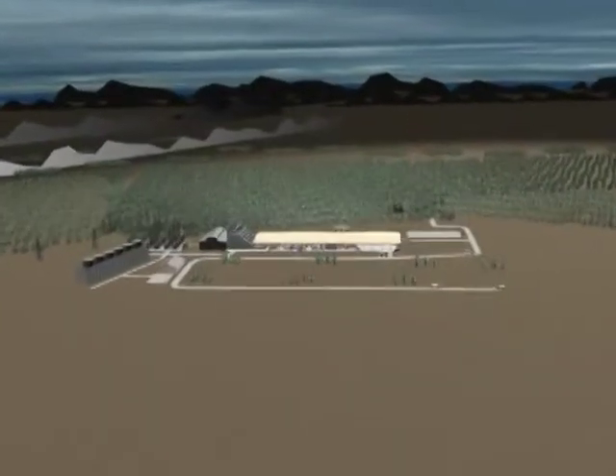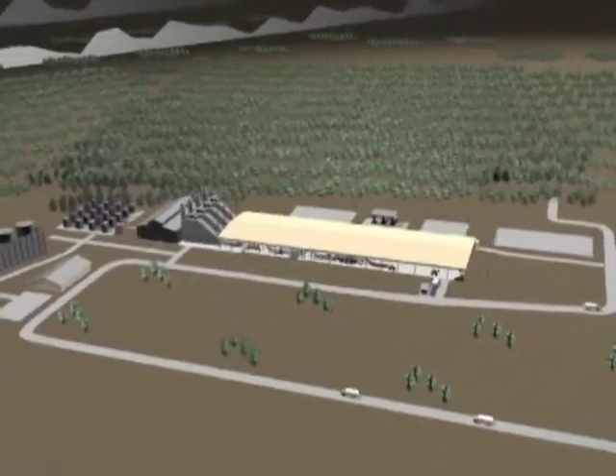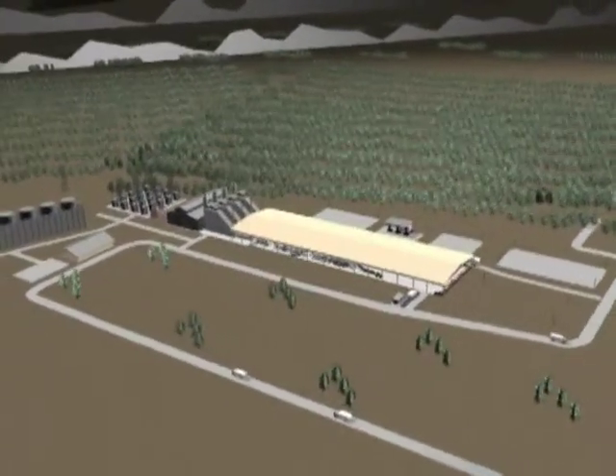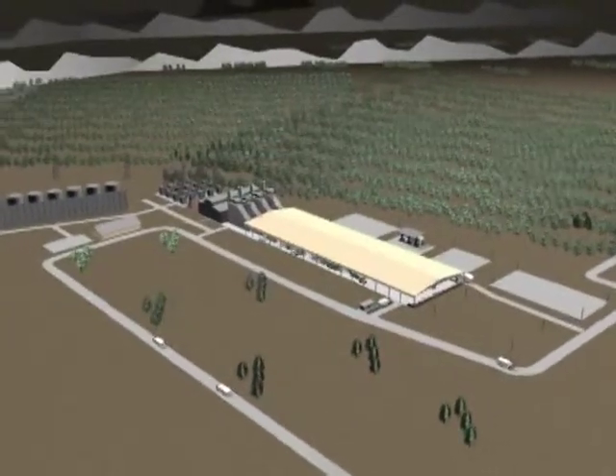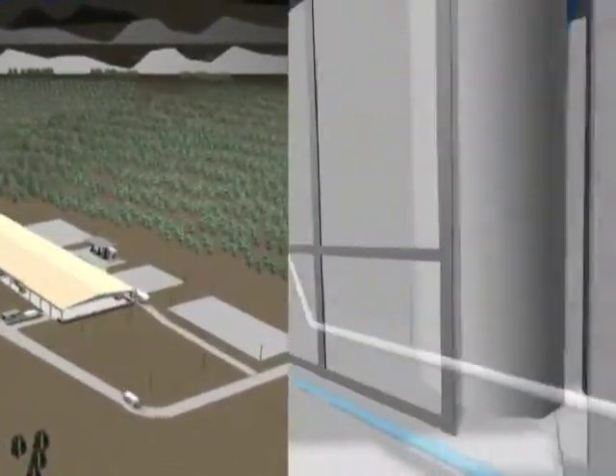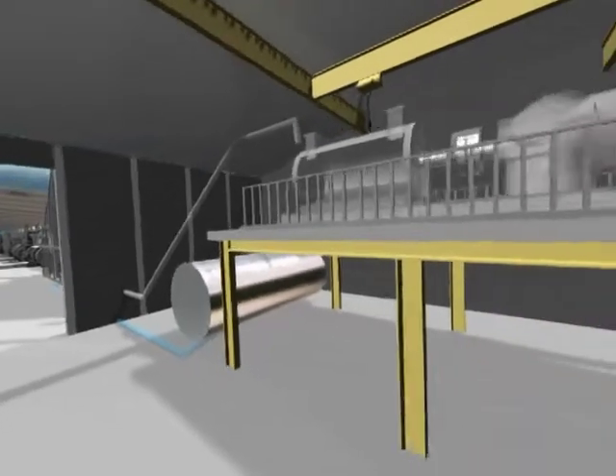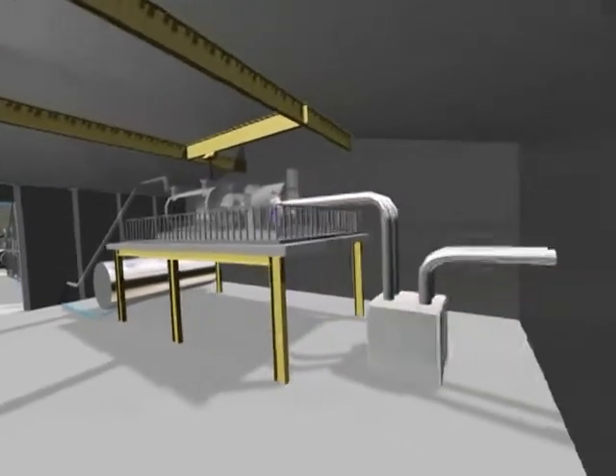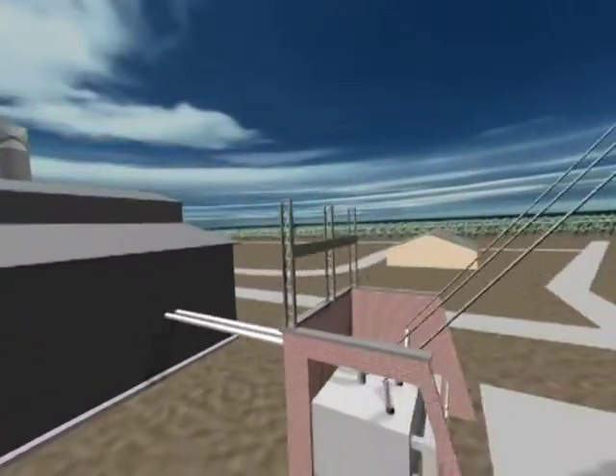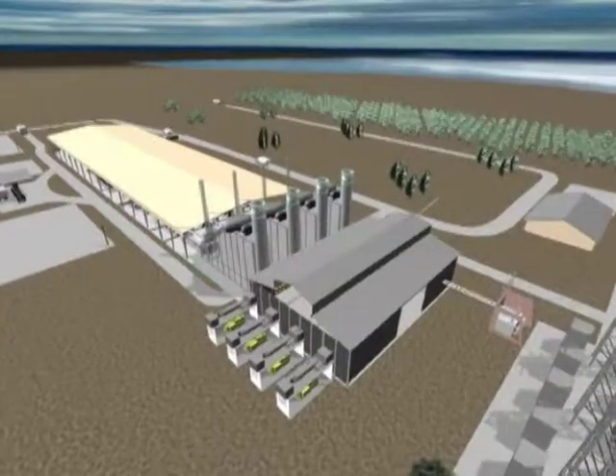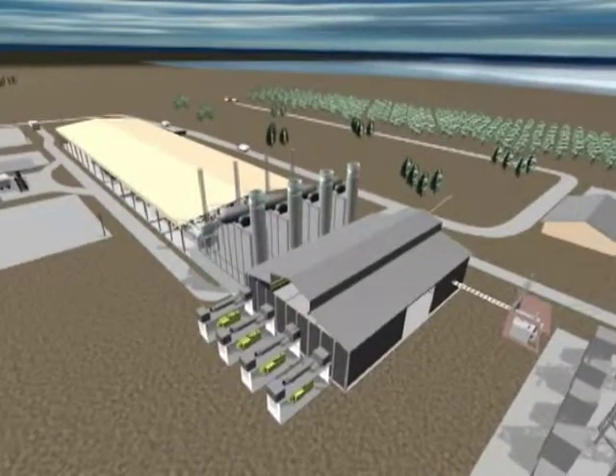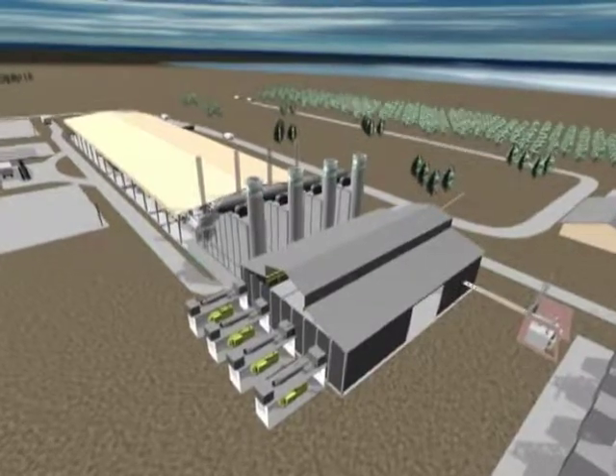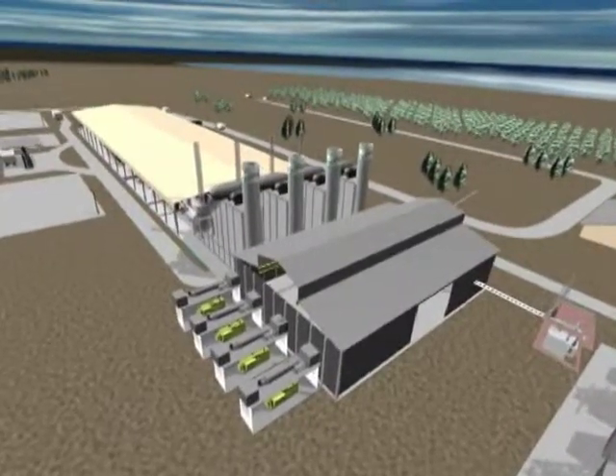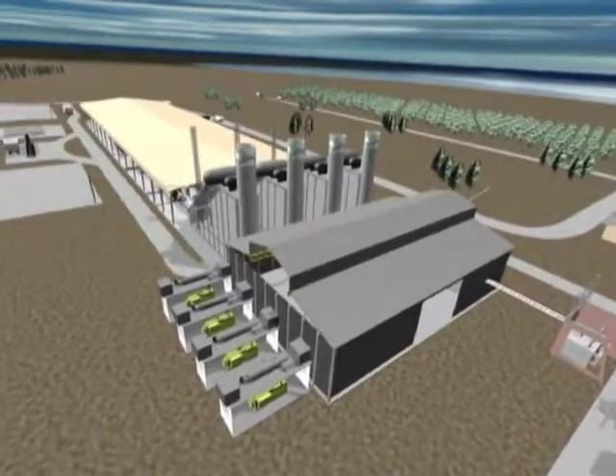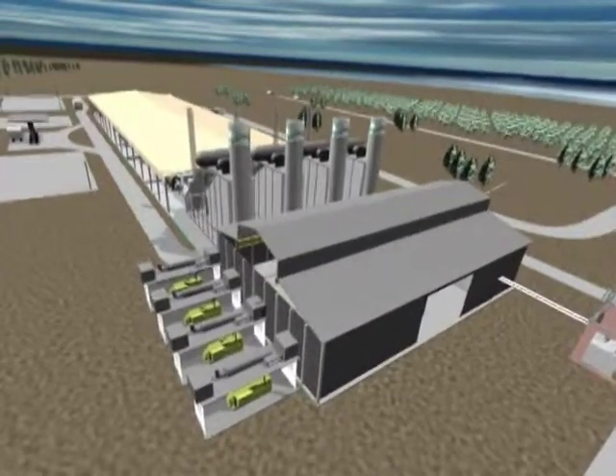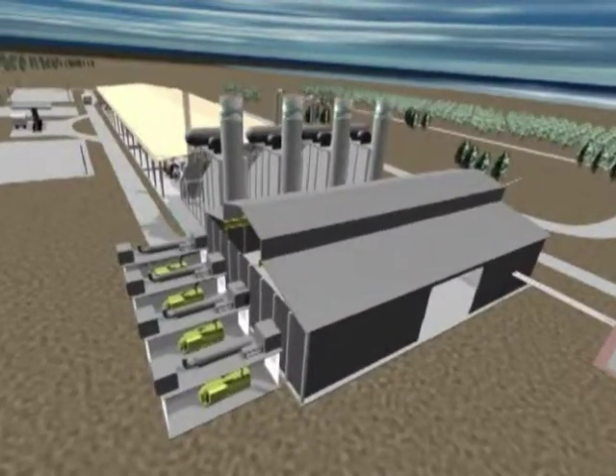With its modular-style design, IES custom engineers a plant to fit the needs of the customer, based on waste disposal requirements as well as energy output needs, whether utilizing the steam for process needs or heating, or for cogeneration to produce clean, renewable power. This plant is designed to handle 1,000 tons of waste per day, utilizing 4 complete lines. Each of the processing lines has a minimum capacity of 250 tons per day, approximately 10.5 tons per hour.